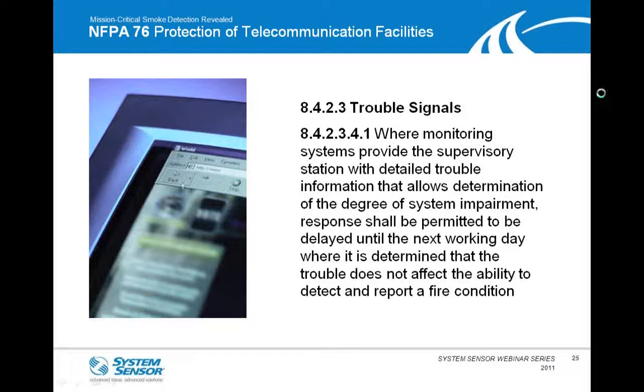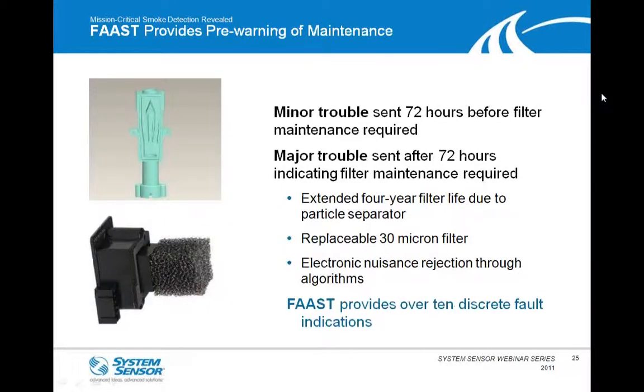So one great example with FAAST that we're able to do is related with the actually replaceable 30 micron filter. Once that filter starts getting dirty to the point where it needs to be replaced, a minor trouble is sent 72 hours before that filter maintenance is truly required. So a great pre-alarm. It gives you very discrete information that tells you that it's due to a filter. It tells you it's a minor fault or minor trouble. So you know that you have those 72 hours.